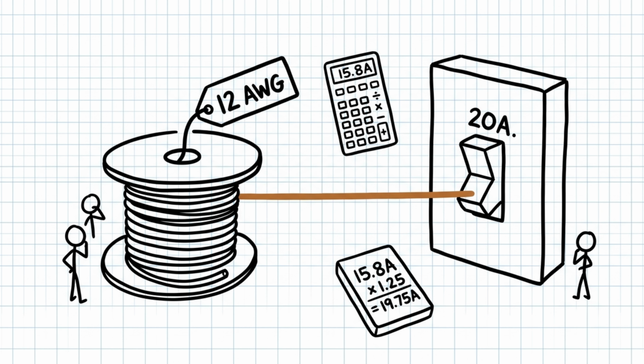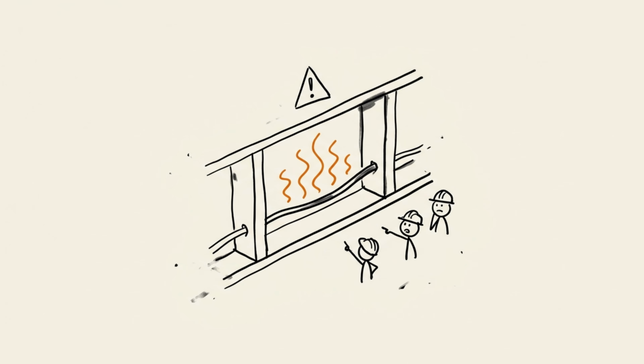Third, the wire and breaker between the inverter and the transfer switch. Continuous loads require both the wire and the breaker to be rated at 125% of that continuous current, so a steady 15.8 amp draw needs wiring and a breaker rated for at least 19.75 amps, which is why that circuit typically lands on 12-gauge wire and a 20 amp breaker. Undersize that wire, and you've built a heat source inside your wall, no matter how correctly you size the battery.